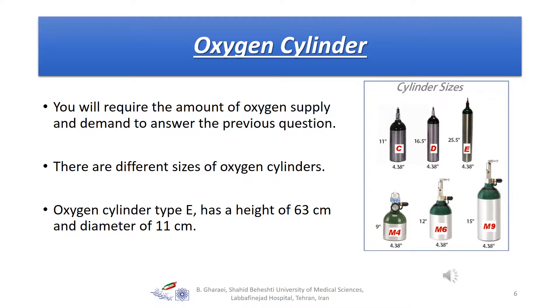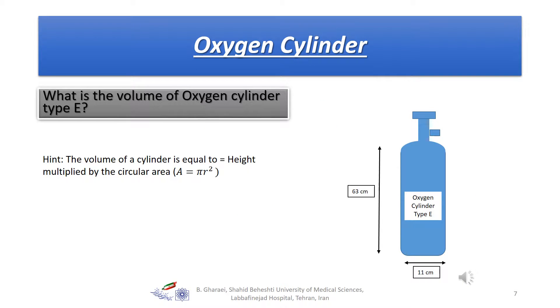To answer this question, you should know your oxygen supply and you should also know the demand. For oxygen supply, you should know that oxygen cylinders come in different sizes. Oxygen cylinder type E, which you can see in the figure, has a height of 63 cm and a diameter of 11 cm. To find out how much oxygen we have in a type E cylinder, we should know the volume of the cylinder.